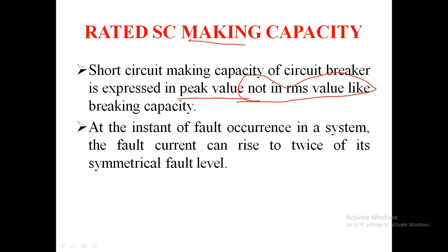In certain cases a circuit breaker may close when a fault is existing. Under this condition, current reaches the maximum value at the peak of the first current loop, so it must be able to close without any difficulty and withstand the mechanical forces developed during closure.